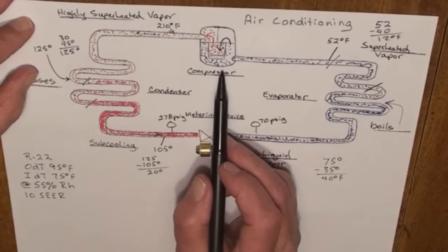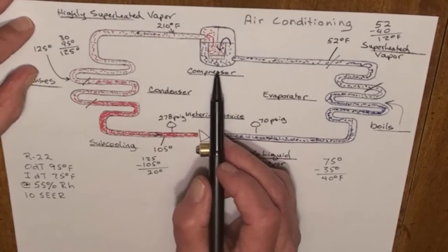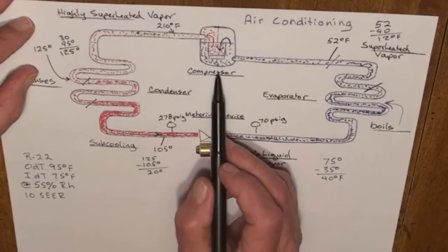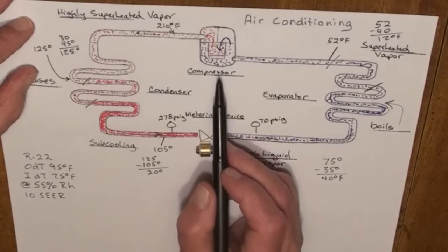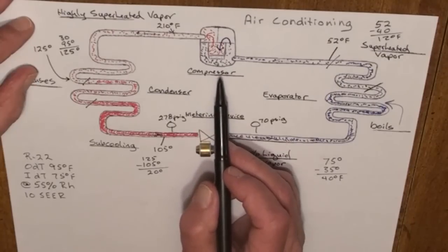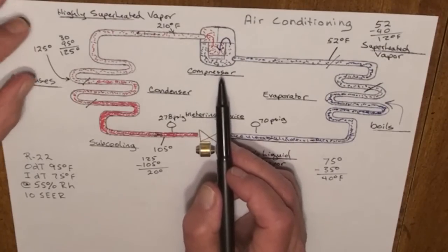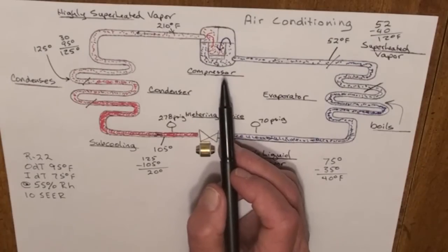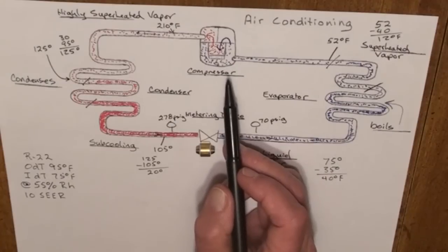It's refrigeration insurance because this piston-driven compressor cannot compress a liquid. It has to compress a vapor. Can't compress a liquid. If you try to compress a liquid, all kinds of bad things happen. On a good day, your compressor would just lock up and quit running. On a bad day, it might break a valve or bust a crank.